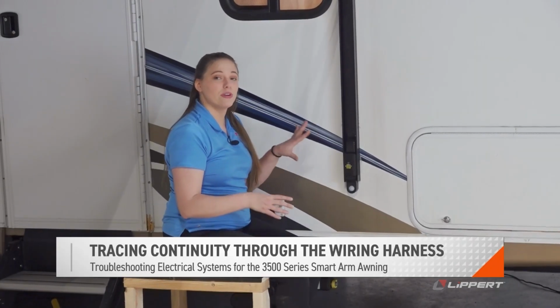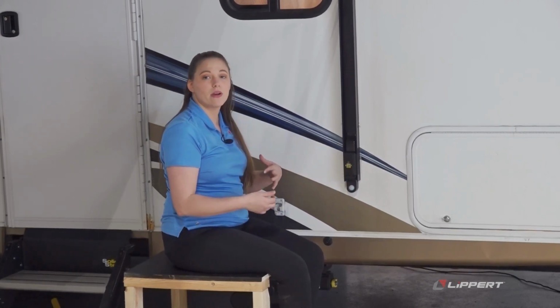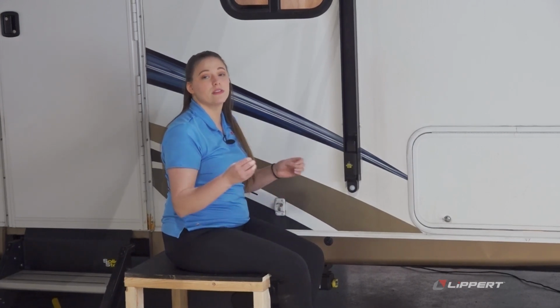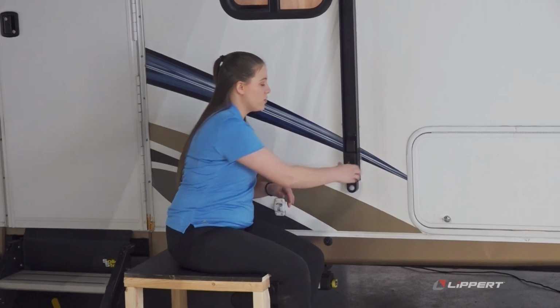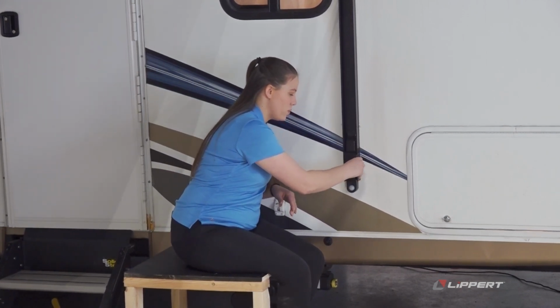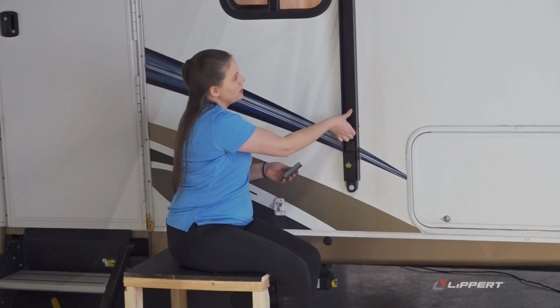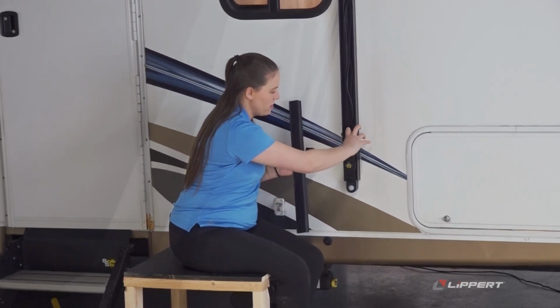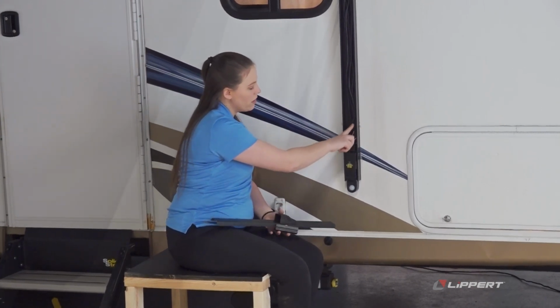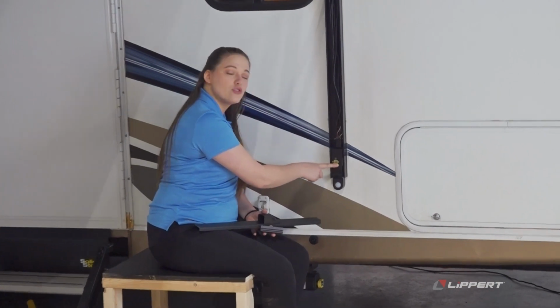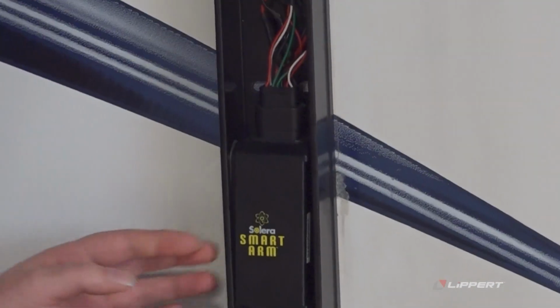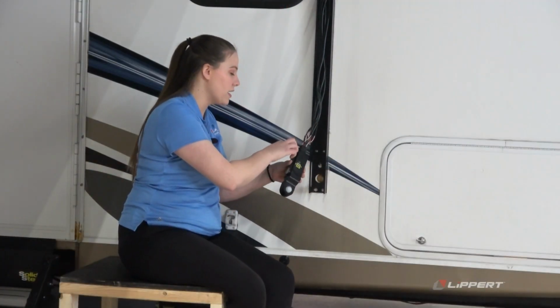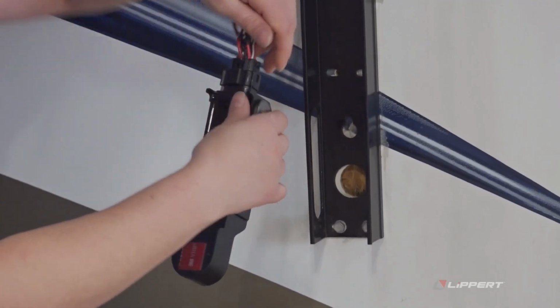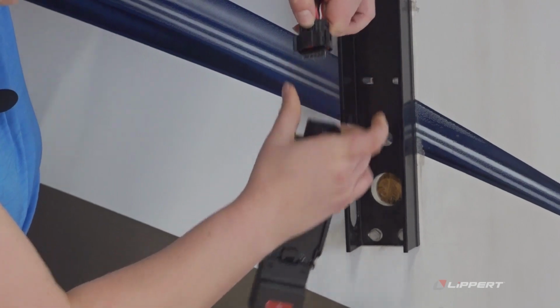Following the electric current through your system, you can check whether a harness is good or not by checking if your controller is receiving power and if it's putting off power to specific components. You can check your controller is receiving power by taking off this holding clip, removing this wire cover, and then removing this cover as well. And here you can see the wire harness connected at that 12-pin connector to your touchpad. You remove your touchpad by pushing it to the side and pulling it out. You can see where it's connected to the IR sensor and it's connected to that 12-pin harness. To disconnect the harness, you press this tab at the top and pull it off.